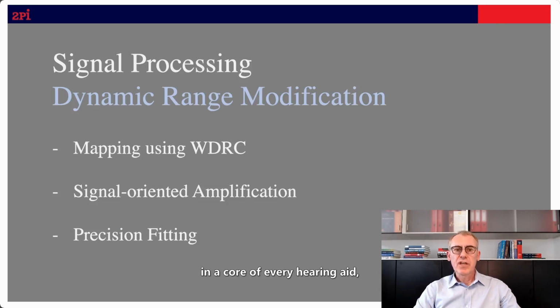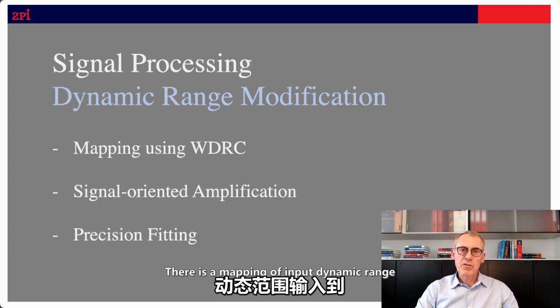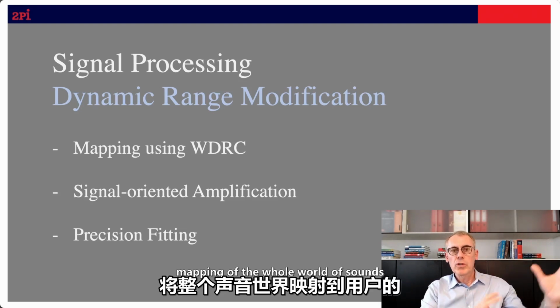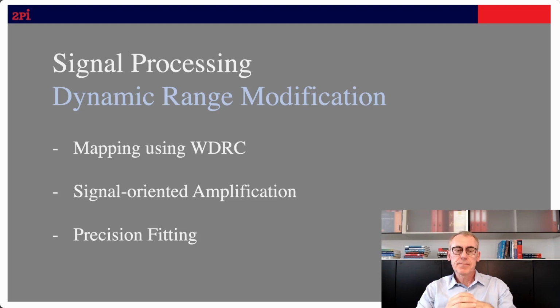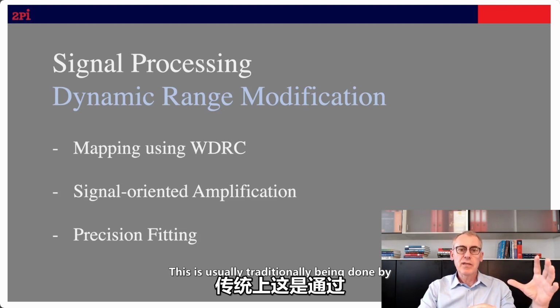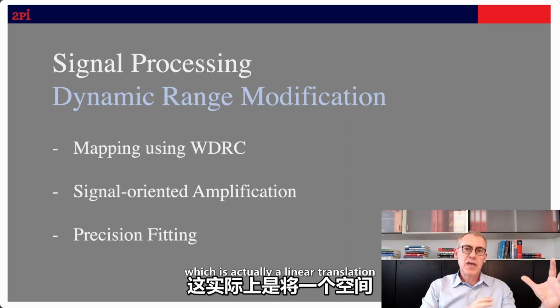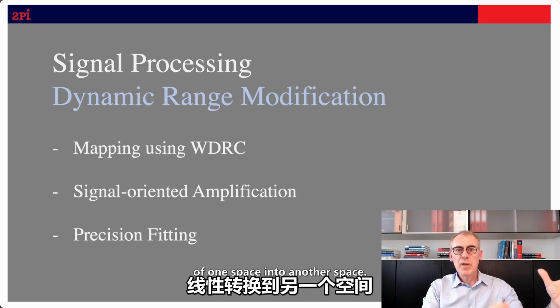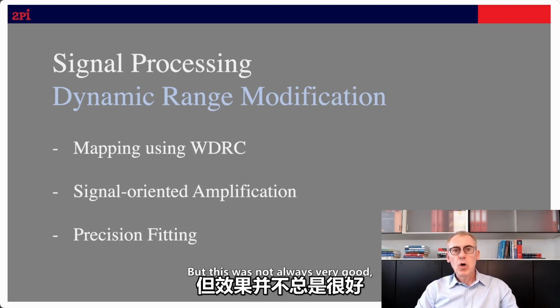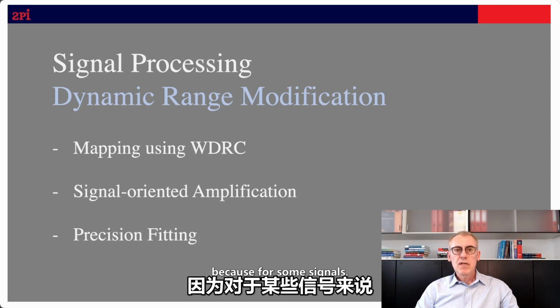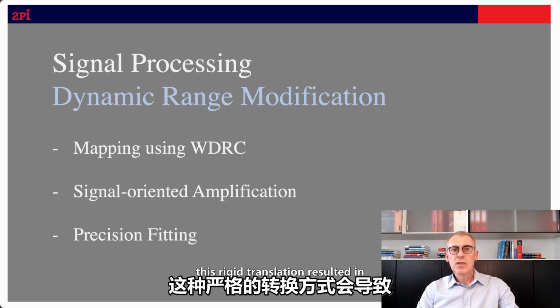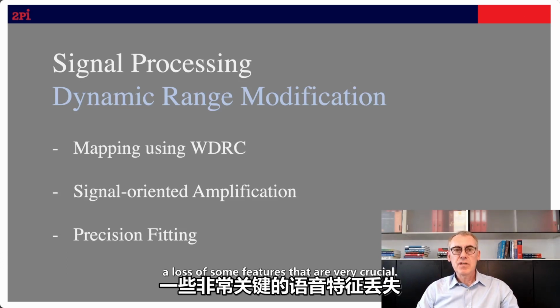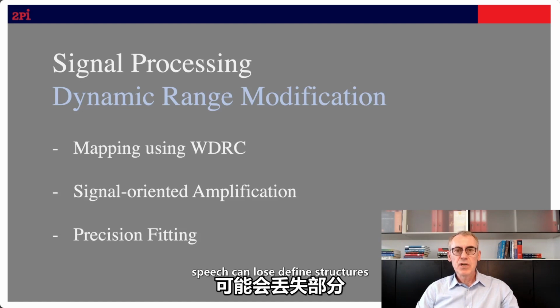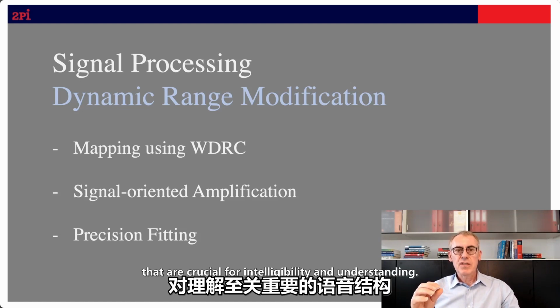At the core of every hearing aid, there is a kind of dynamic range modification. There is a mapping of the input dynamic range to the output dynamic range, a mapping of the whole world of sounds into a residual hearing. This is traditionally done by wide dynamic range compression, which is actually a linear translation of one space into another space. But this was not always very good, because for some signals this rigid translation resulted in a loss of some features that are very crucial. For example, speech can lose the fine structures that are crucial for intelligibility and understanding.